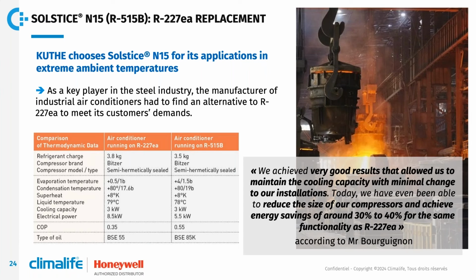A second example for another industry. So here we have the company showing the use of R515B in replacement of another refrigerant used before, which is R227ea. Here, this is an industrial air conditioning, and you see the conditions in terms of temperature, especially for the condensing temperature. We have a very high temperature. The condensing temperature here is about 80 degrees C.